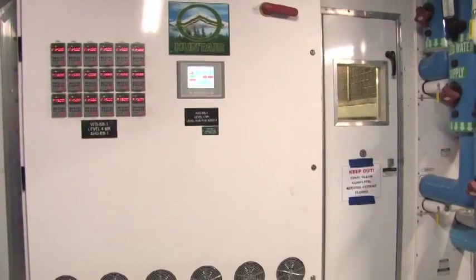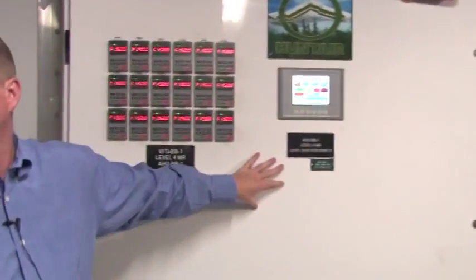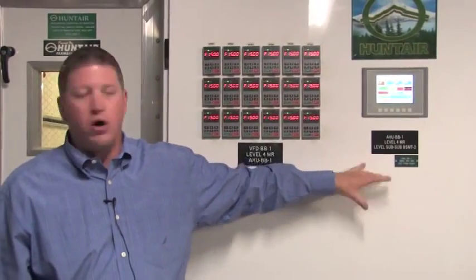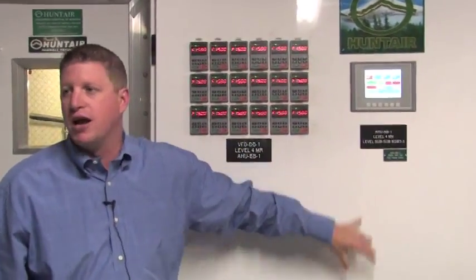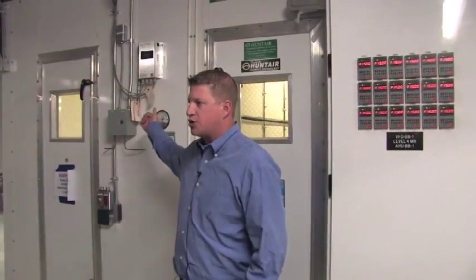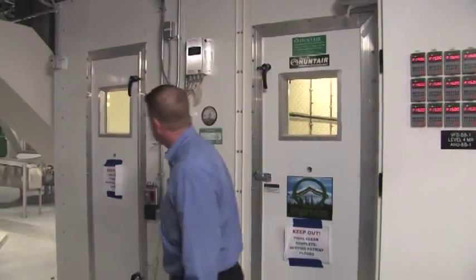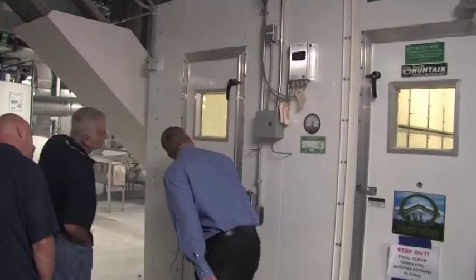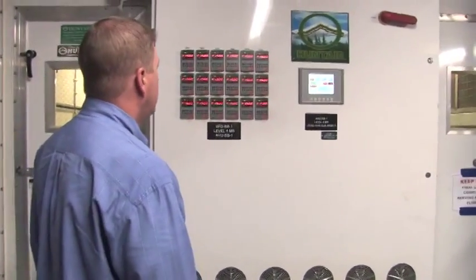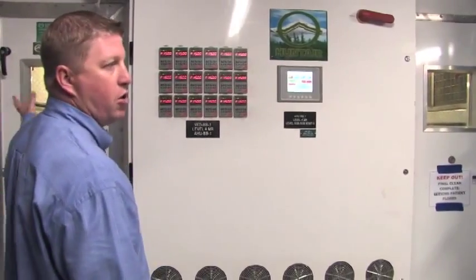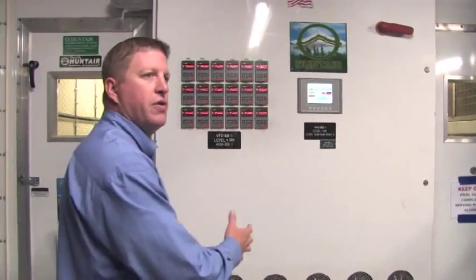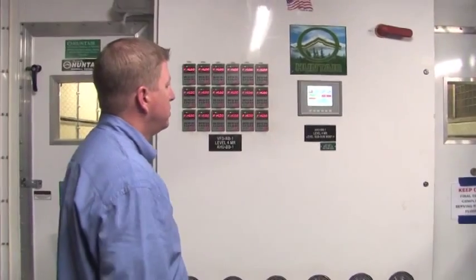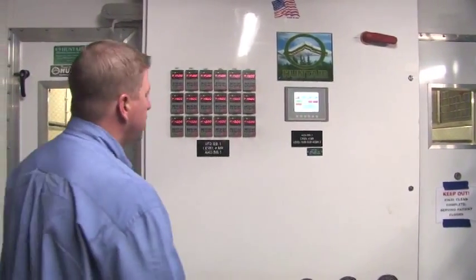All right, so I put it into remote control here. The BMS is controlling it at this point, so it's giving it a start command. At this point, the discharge damper should be controlling open, which they are. They take about a minute. So once those dampers come on, the end switch will make, it'll allow the unit to come on. That alarm will clear once the damper's made.